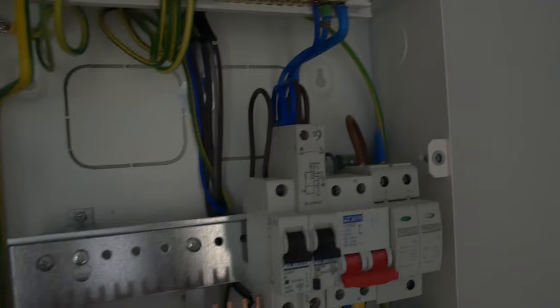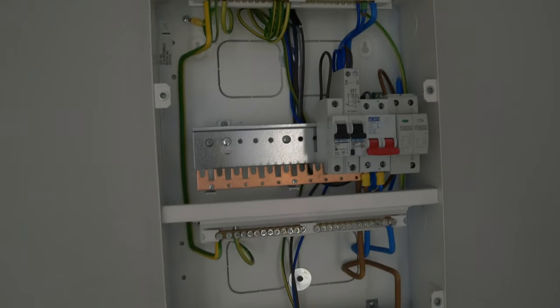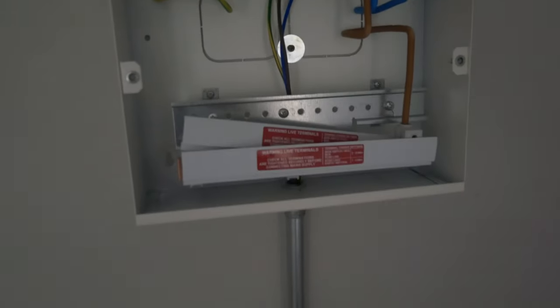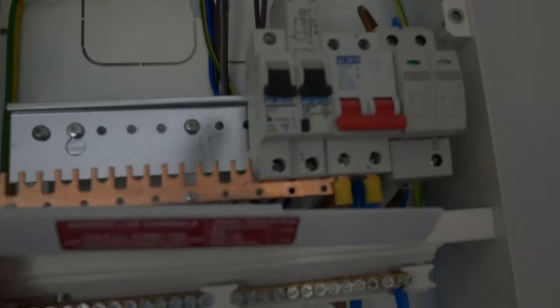You can see we're pulling our singles in, dropping down each tube into the sockets along our radial. So it is a radial circuit. You'll see this last socket here is end of line. We've also pulled our conductors through and into the light switch, and Nathan's got those cables back into the consumer unit. You can see he's dressed those away into a couple of breakers. We are going to expand on this. We'll have a look at that later on in this video as well.